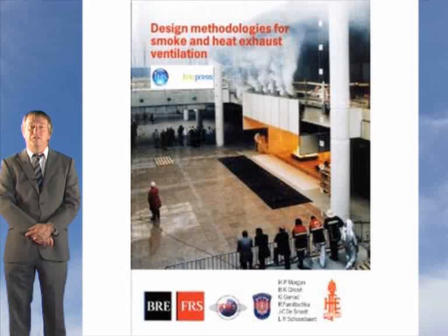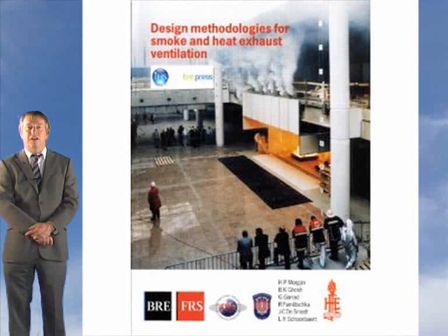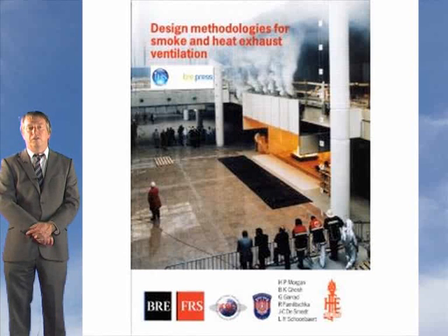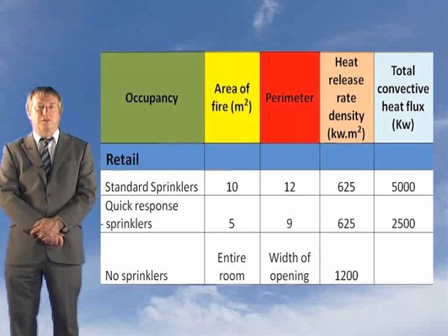There are a number of guides where you can obtain relevant information. One such source is BR368, Design Methodologies for Smoke, Heat and Exhaust Ventilation Systems. In table 3.3 in this document, you can find some information on design fire sizes. Here are some examples extracted from this table 3.3 in BR368.